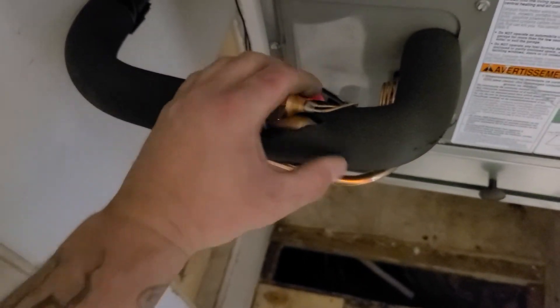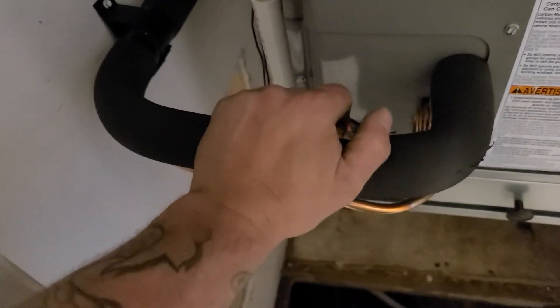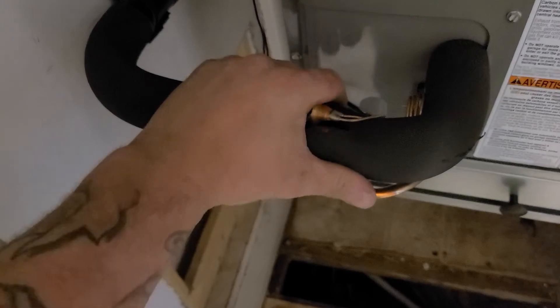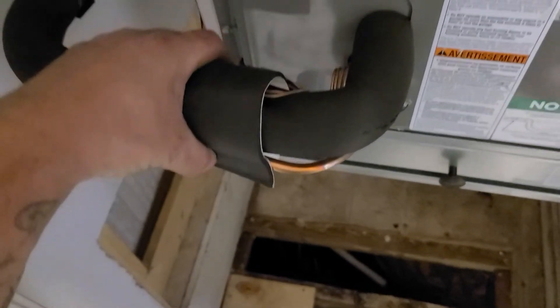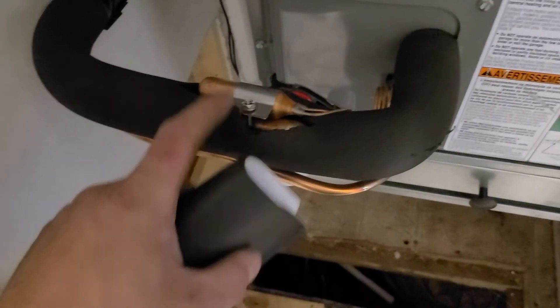In our case, we're looking at the 12 o'clock position. We're going to put ours in the 10 o'clock — so it's towards the back — and then we're going to wrap it all up and seal it up. We're going to use the foam that it comes with, because that will help seal it to the pipe so it gets an accurate temperature reading.